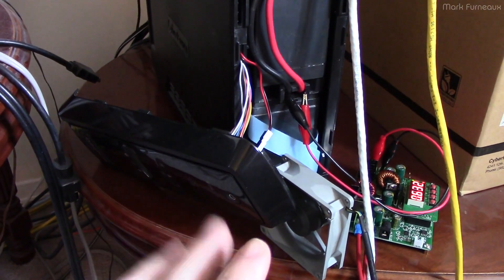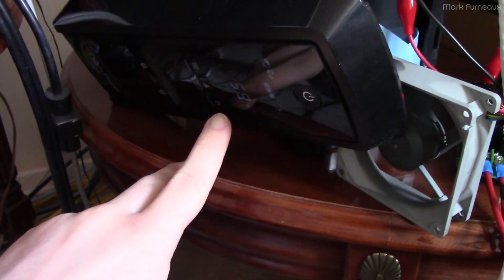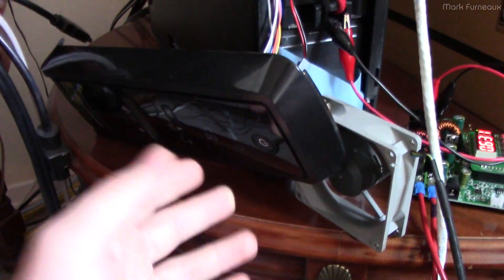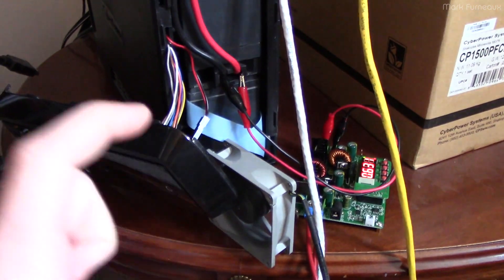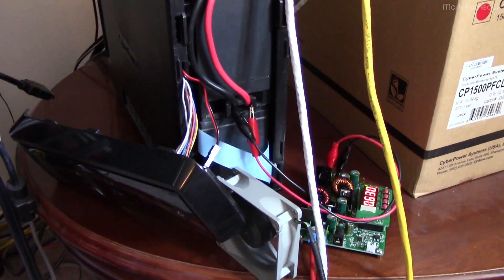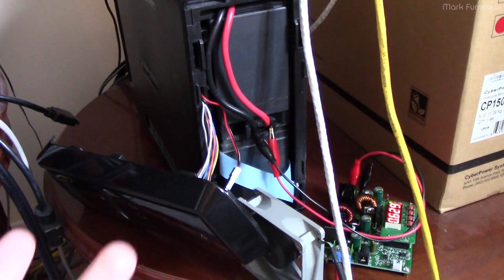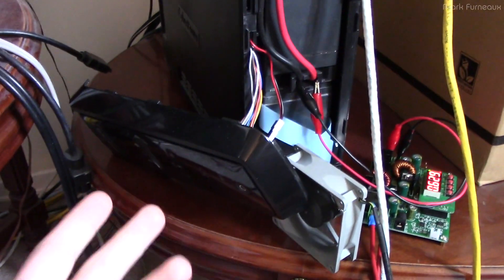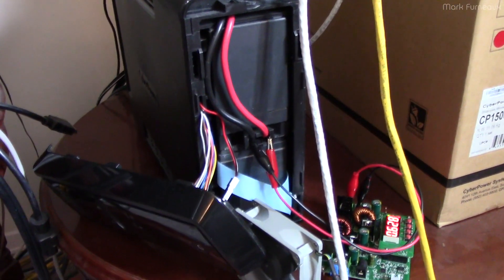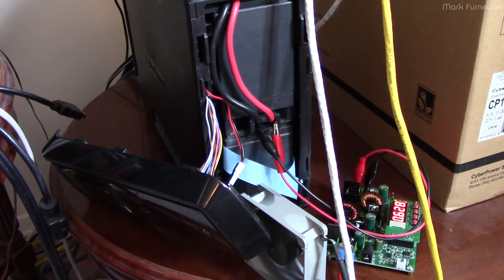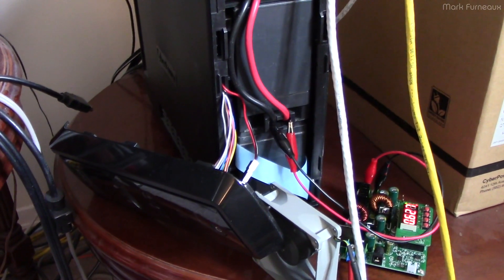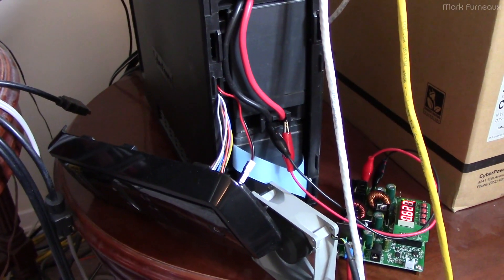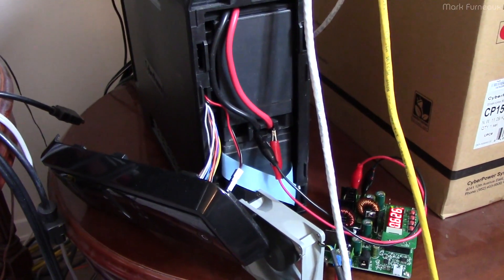Of course, it has a battery percentage readout, and that, during discharge, is going to use the voltage across the batteries using the lead-acid discharge curve to estimate how much charge you have left as far as percentage goes. But when charging, it is entirely fake, and I didn't realize that until today.